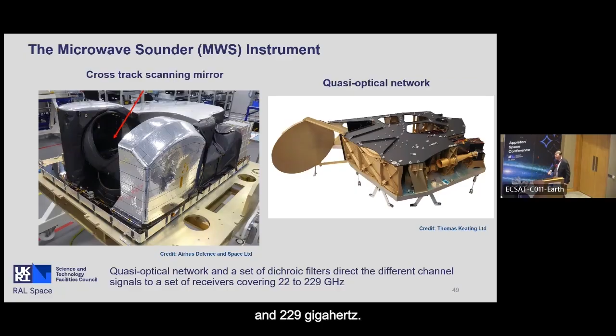And what's inside is a quasi-optical network produced by the SME Thomas Keating Limited. So we have a mirror that takes the radiation from the molecules and sends it into this network of mirrors and dichroic filters, frequency selective surfaces, that direct the radiation to a number of ultrasensitive receivers. So it goes from free space into these things called feed horns, and we bolt our receivers on the waveguide output there. There's a set of receivers in there covering between 22 and 229 gigahertz.